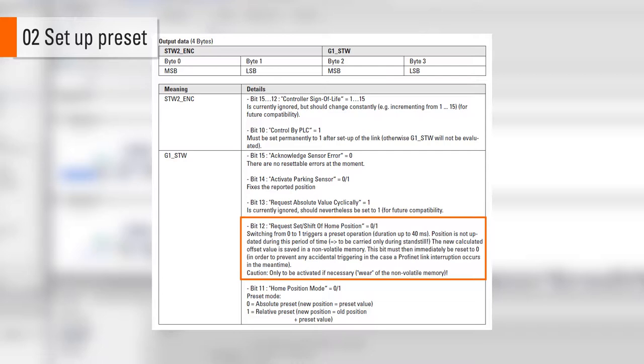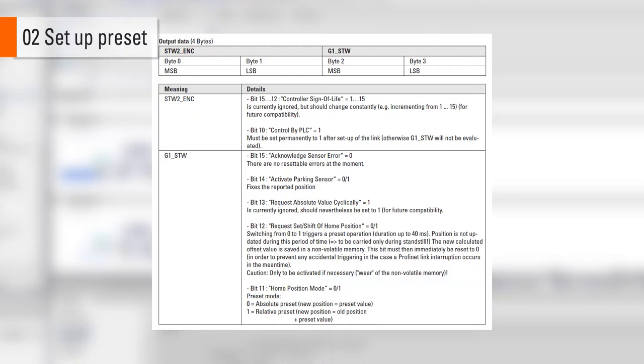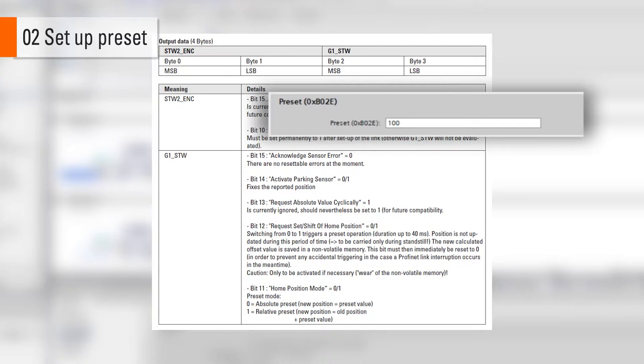Bit 11 determines the preset mode, absolute or relative. The actual preset value is not contained in this telegram. If the preset is executed, standard telegram 81 uses the preset value contained in 0x802E.